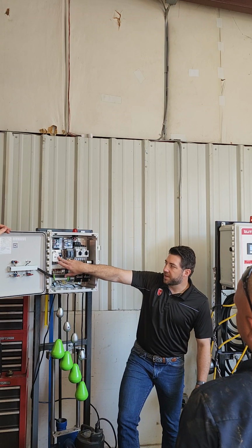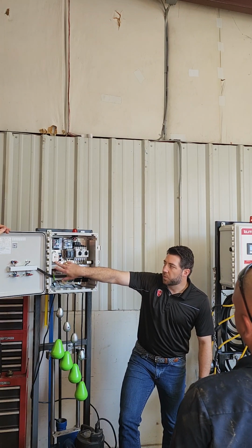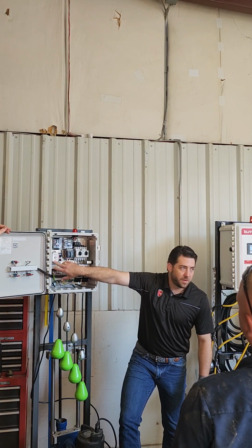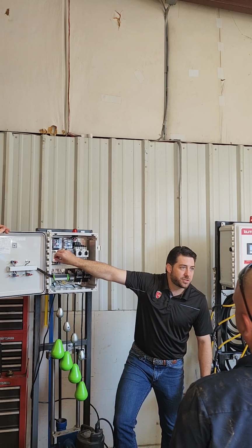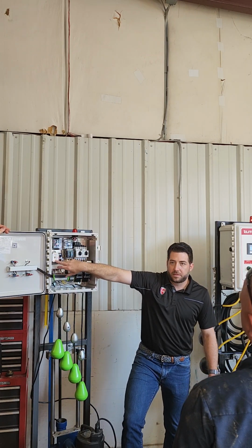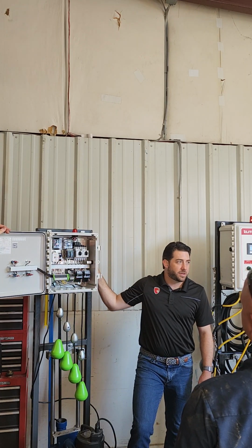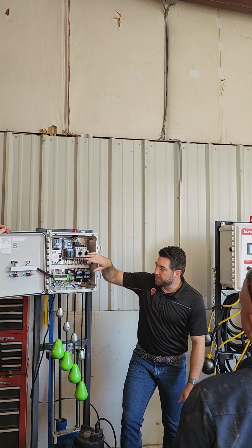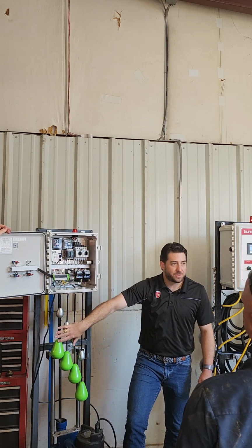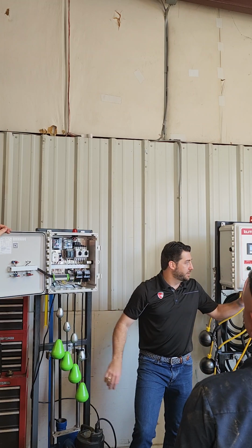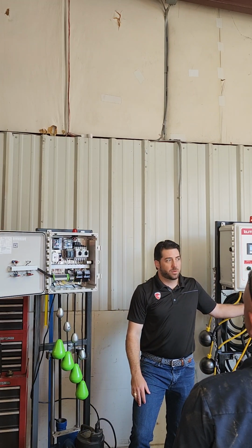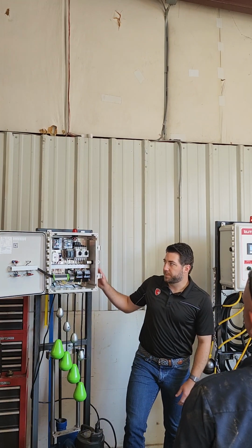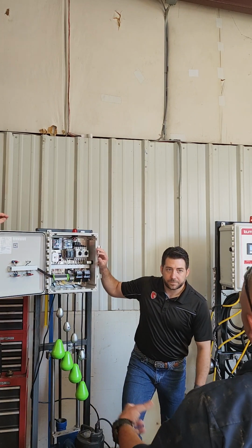You want to leave that on alternate. If you force it to one or the other, then it's always going to run that pump first. So if you're doing service or something and you need one pump to be the lead, that's how you can do it, using that alternating relay. Okay. With this type of panel, we are sending 120 volts out to the floats. With a panel like this, we're only going to be sending 24 volts, just because it's coming off the PLC. Is there ever a time to run both pumps at the same time?